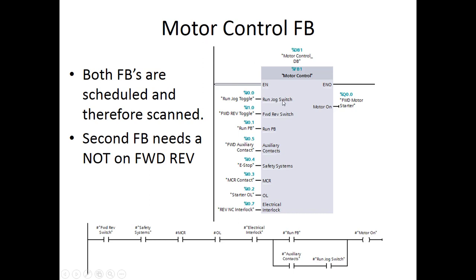You took this motor control function block and scheduled it twice to get two data blocks. You generated it with all your tags and ladder logic, then scheduled it twice — the first time for the forward starter, the second time for the reverse starter. The second time you schedule it, you still use the same run button, same switch, switch the auxiliary contacts to the reverse, same e-stop, same MCRs, same overload. So you basically reuse just about all of the IO by scheduling this twice.